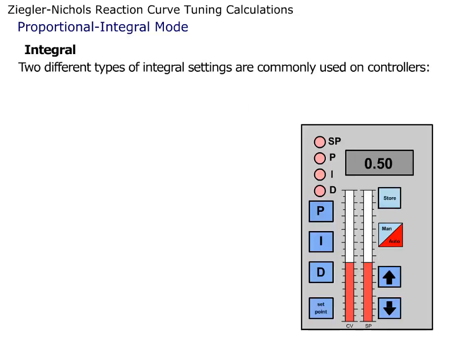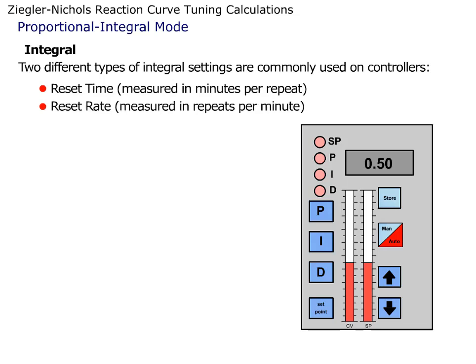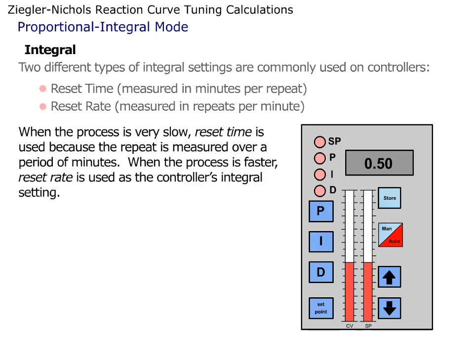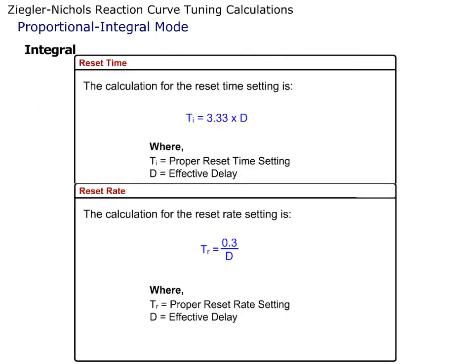Two different types of integral settings are commonly used on controllers: Reset Time, which is measured in minutes per repeat, and Reset Rate, which is measured in repeats per minute. When the process is very slow, Reset Time is used because the repeat is measured over a period of minutes. When the process is faster, Reset Rate is used as the controller's integral setting. These are the formulas for the Reset Time and Reset Rate settings in the Proportional Integral mode.